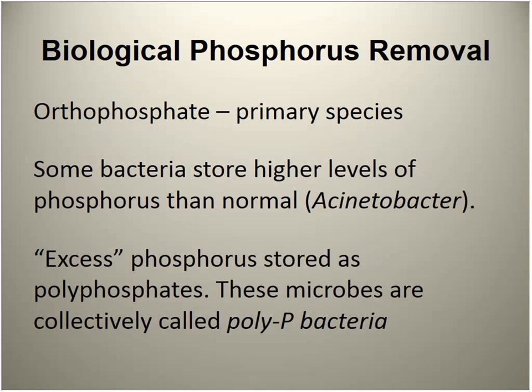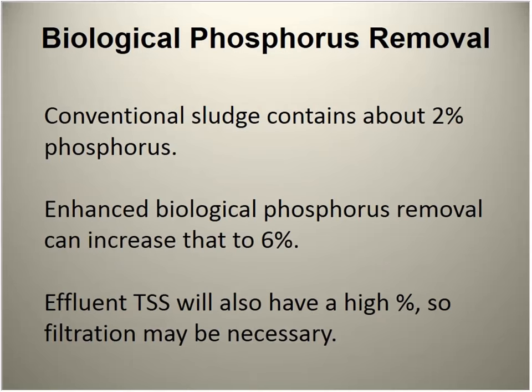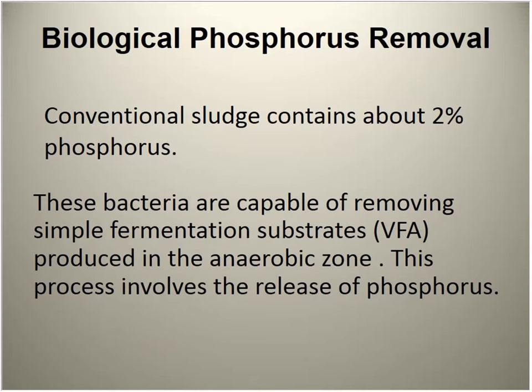The phosphorus we're dealing with is primarily orthophosphate. Organisms called poly-P bacteria can store excess phosphorus under the right conditions. Typically our sludge is about 2% phosphorus, but by manipulating these organisms to take up excess phosphorus, when we waste them they're actually about 6% phosphorus — that's how we remove it biologically. It goes out with the sludge. However, if there are clarifier upsets causing elevated suspended solids in the effluent, the phosphorus load in those solids will be elevated as well.